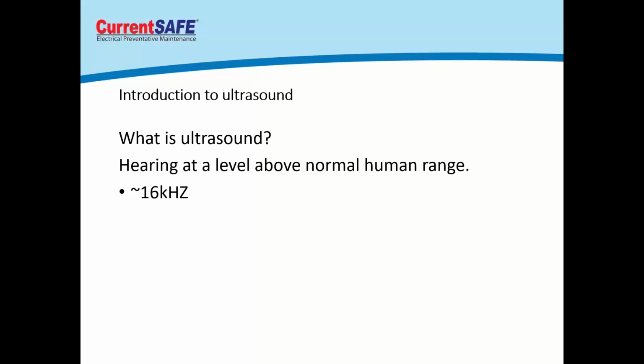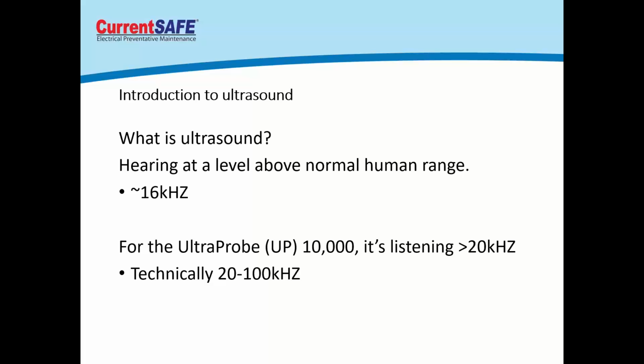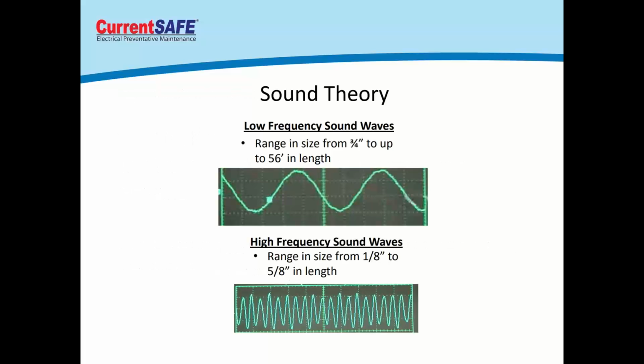So what is ultrasound? Really, it's hearing above our normal human range. Normal hearing for a human stops at around 16 kilohertz. The ultrasonic detection that we utilize is listening in what's called the ultrasonic world, which means 20 kilohertz to 100 kilohertz, above what we can hear with our normal ears, for electrical anomalies like arcing, tracking, and corona. This allows us to detect things that we can't hear. That's why it's called ultrasonic. It's above our normal hearing range. We use the UltraProbe 10,000 from UE Systems, listening in the 20 to 100 kilohertz range.